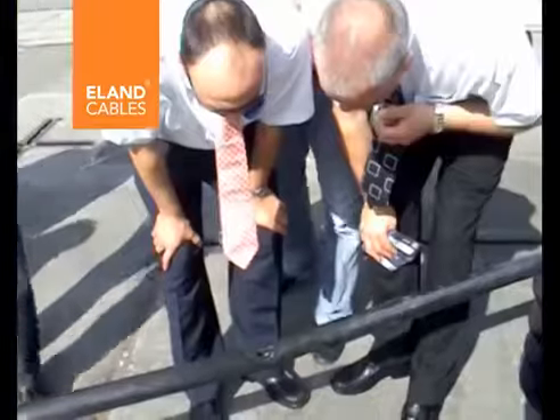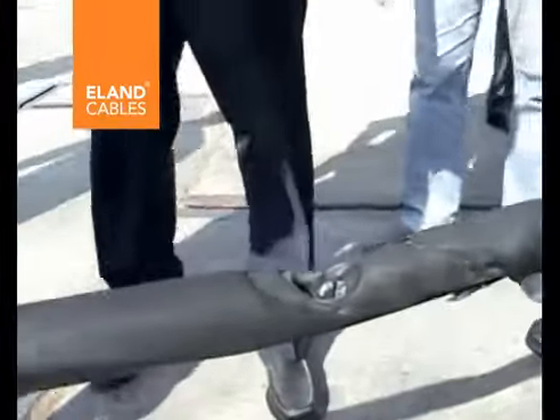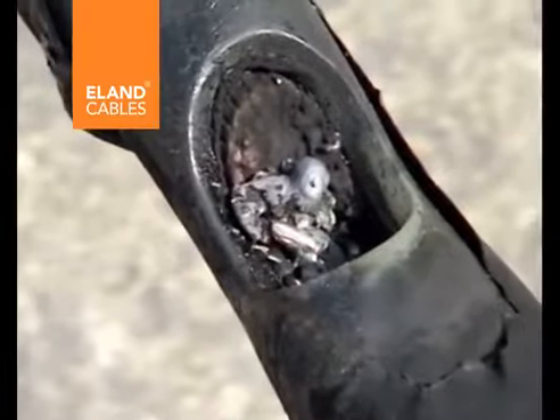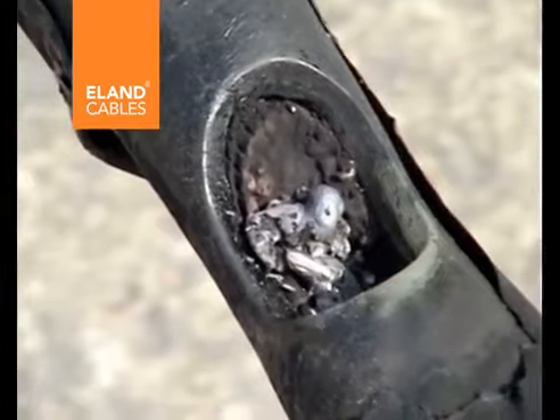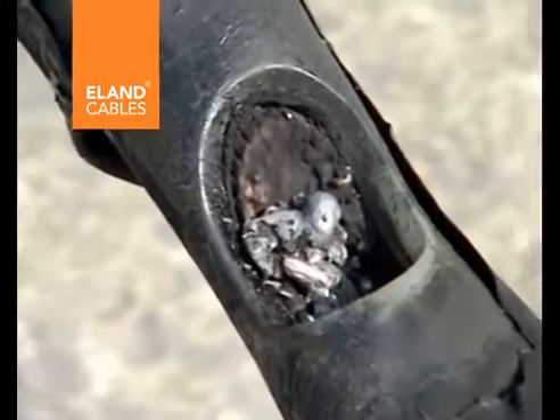The pulsation visible in the arc was the alternating current flow through the phase conductor down to earth. The arc reached approximately 1,500 degrees Celsius in 0.2 seconds. The arc systematically burnt the outer sheath, the copper wire screen, and all layers down to the phase conductor. Here you can see the remains of the steel spike melted into what was left of the conductor.